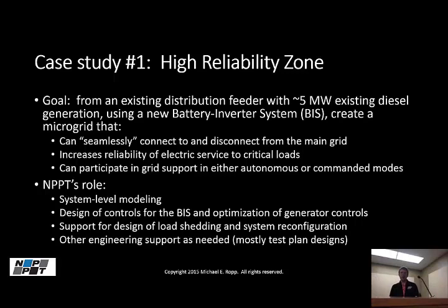The objectives of the project were we wanted to be able to do a seamless on- to off-grid transition. Part of the reason for that was because on this feeder there was a prison, the city 911 call center, and a military facility, all of whom have a legitimate need for blinkless power. And we keep laughing that the one that really needed the blinkless power was the state lottery computer center, which was on this feeder. But then we want to be able to basically increase the reliability of service, right, is the entire key of this.